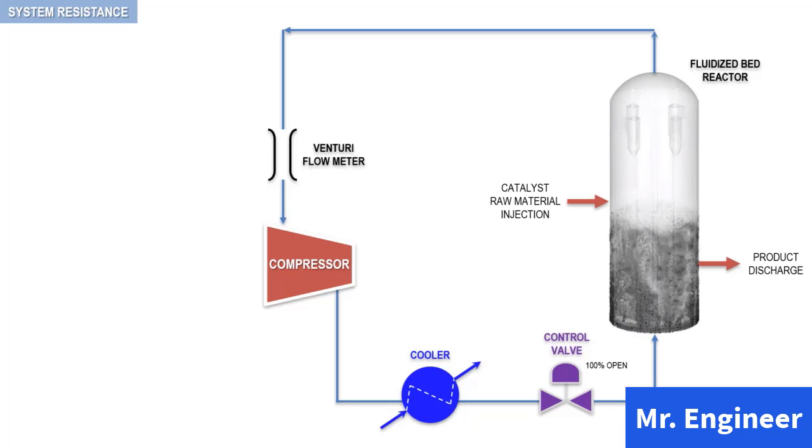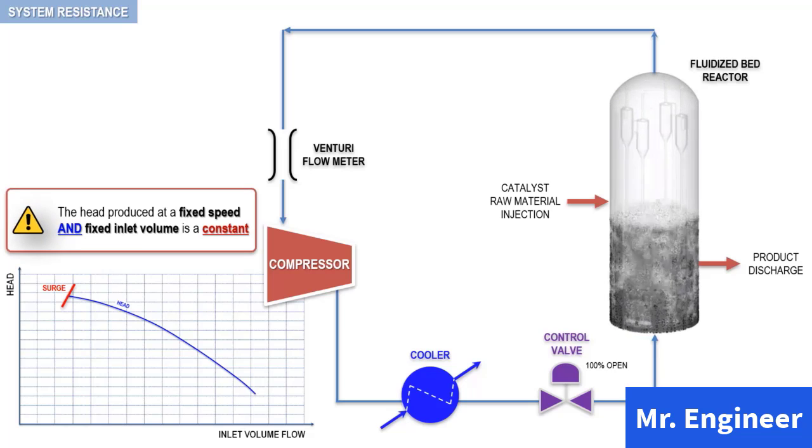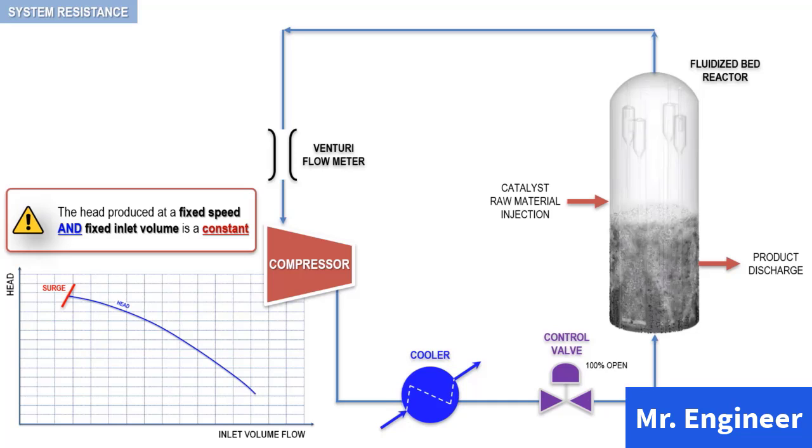In our case, we have the compressor performance curve as provided by the manufacturer for rated inlet conditions. It takes the form polytropic head versus inlet volume flow. Since the compressor operates at a constant rotational speed, then the head produced by the impeller for a given inlet volume flow is a constant, regardless of the inlet conditions. This statement will form the basis upon which we can derive the procedure accounting for the effect of system resistance.